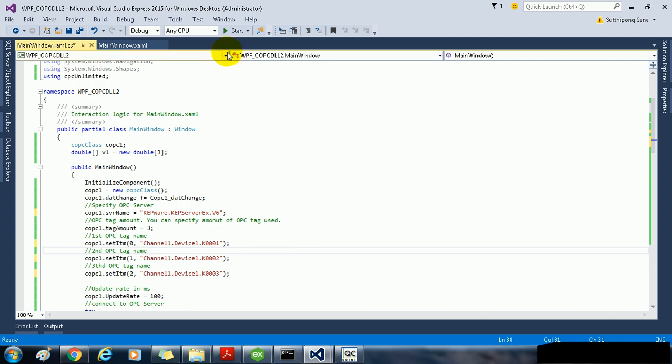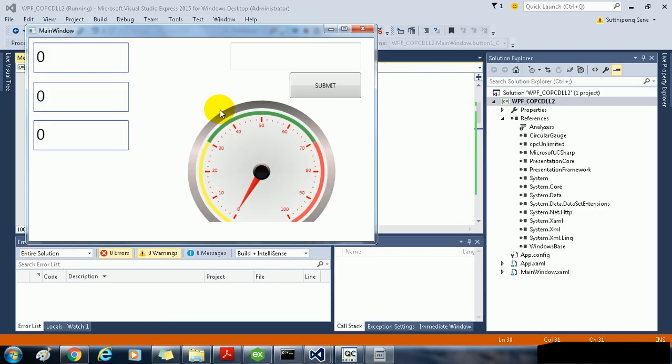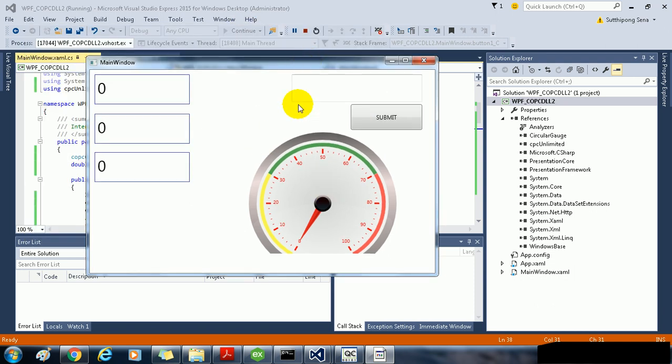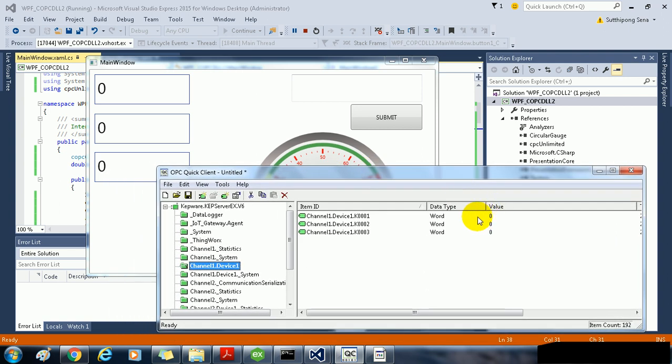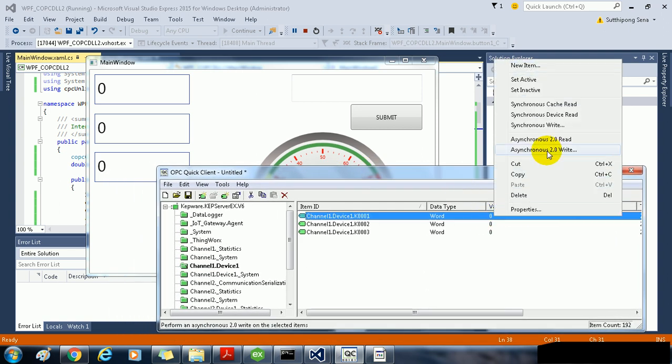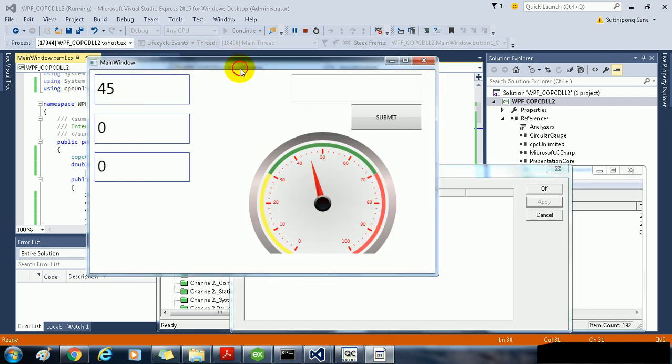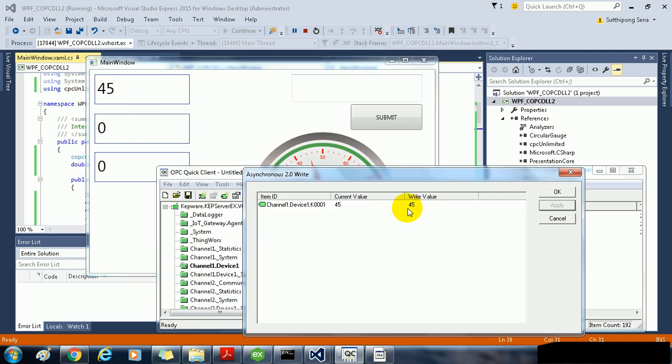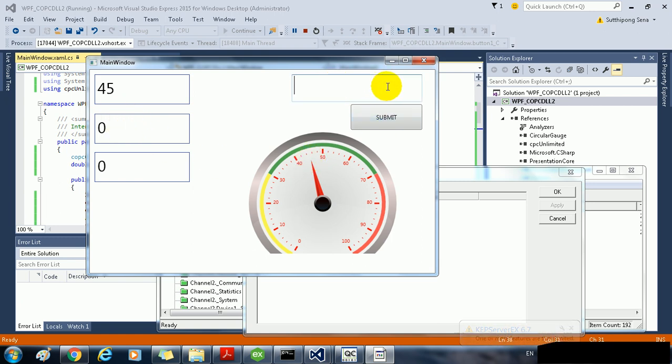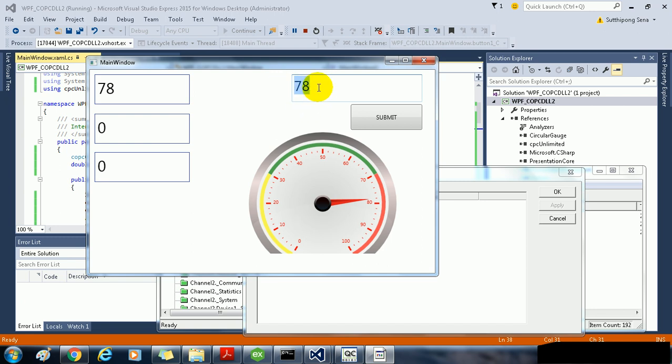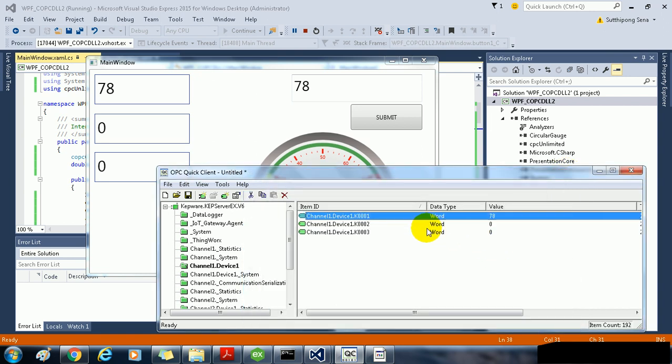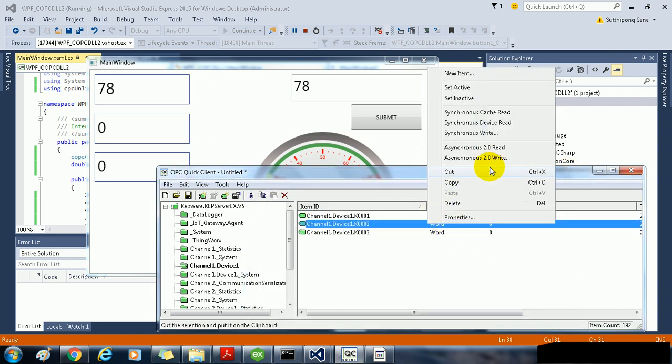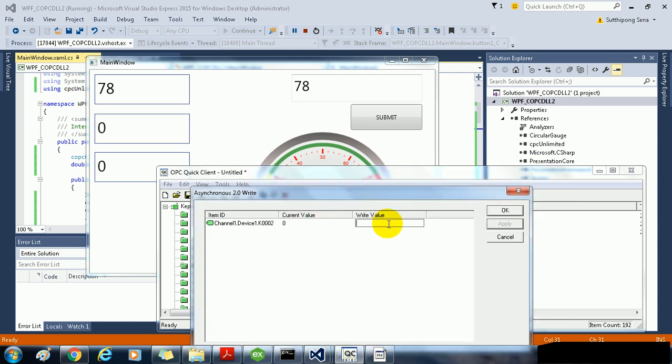Okay, now save. Please make sure that you have typed correct name of the OPC server and the channel name. For example, in Kepware it is the Kepware quick client that shows the OPC server name and the channel name. In this example I had typed incorrect name of the channel here, it will not connect to the channel. Then I have to correct the channel name. Okay, now start testing. Okay, now we connect to the OPC server in the quick client. We can write the OPC tag. For example, I type 45 and then apply. In the application it will show the value of the OPC tag, the current value, and the gauge will show the current value of K1 and K2. If I submit some value, then K1 will change to the number that I have input to the text box. Now trying to test another test. Okay.